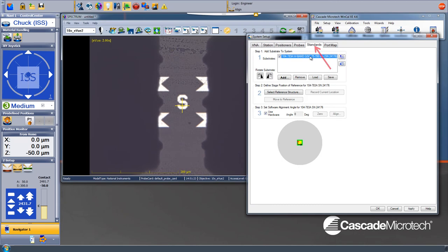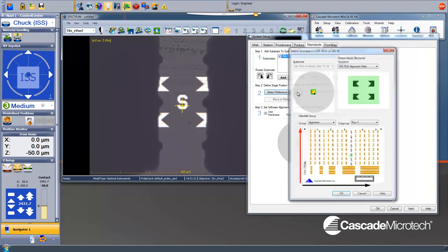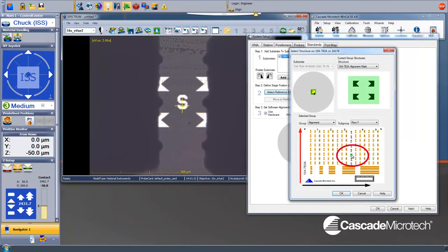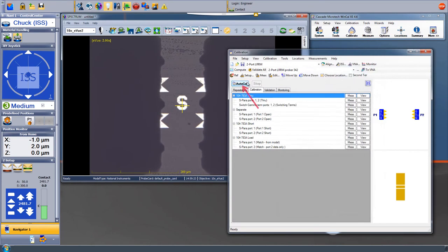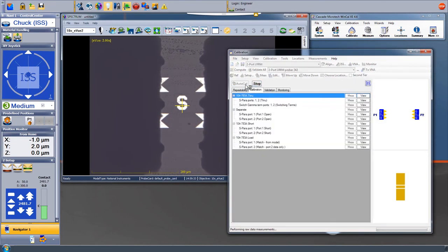Under the Standards tab, we point the program to the precise calibration structure being used. We can also tell the software what is our starting position. In this case, we are set to an alignment mark in the middle of the substrate. Then we click the Auto-Cal button to initiate the process.